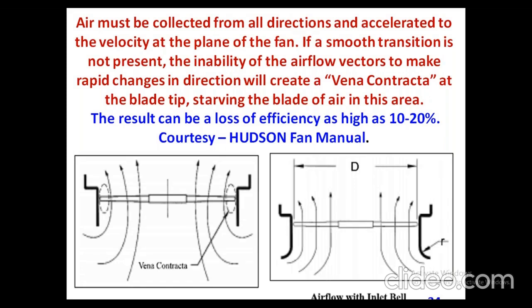This is also a critical area. With this axial flow fan running, the vena contracta is happening and the short circuiting is happening; this is a loss. This has to be corrected at the generation point in the axial flow fan.